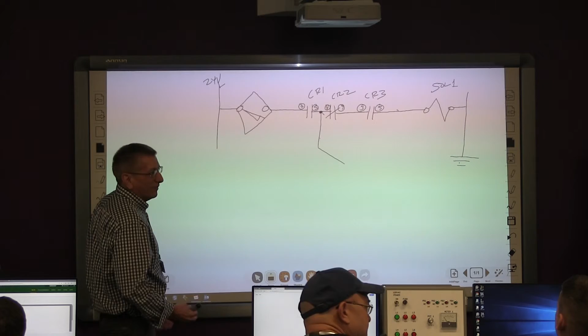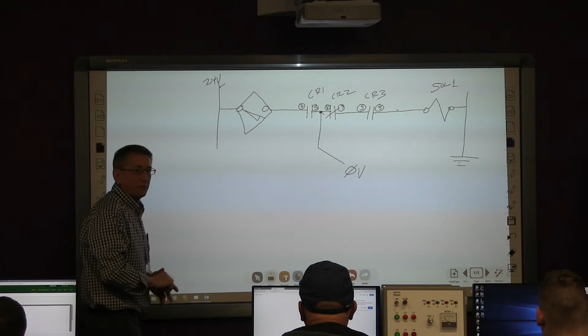Okay, so let's say we measured this point and we got 0 volts. This relay is energized - what's the probable cause? You could either have something wrong with the relay, or a broken wire.